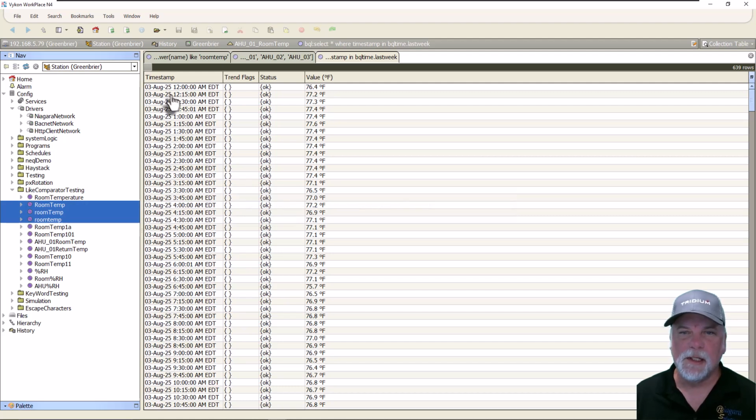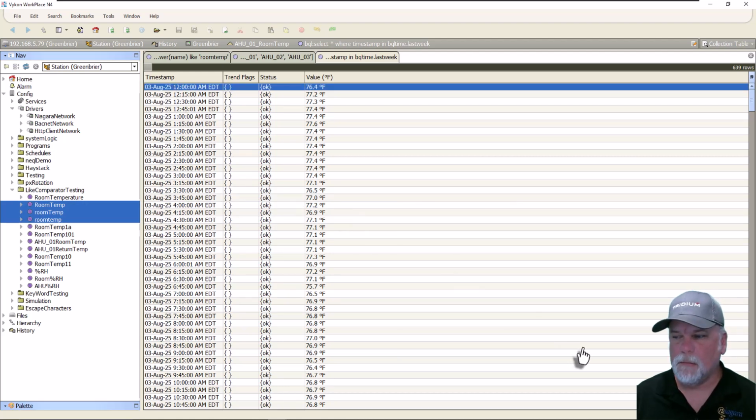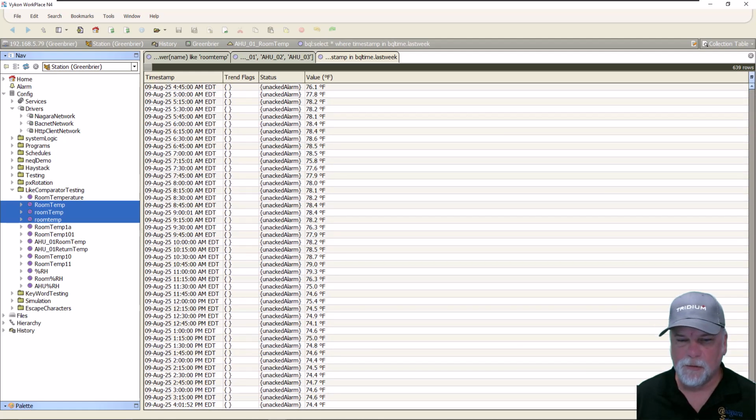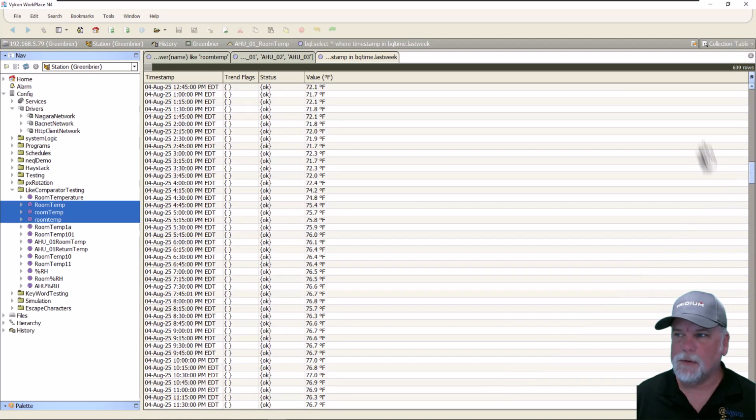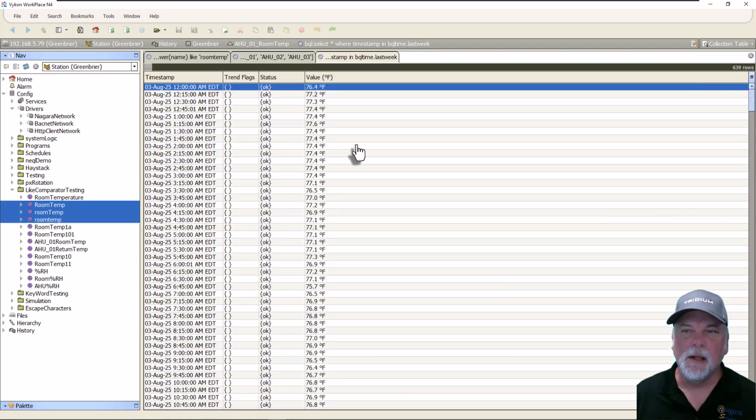So you can see in this case, the start of the previous week was 3 August at 12 a.m. And then it has 639 records, which is 672 in a week, but it's going only till 4 p.m. on the 9th. So I must have had the station not running and collecting histories at some point in time last week.